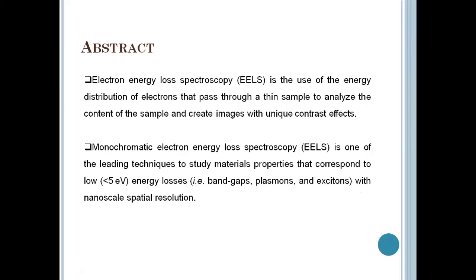These characteristics are observed in different energy regions depending on the energy loss. Electron energy loss spectroscopy is the use of the energy distribution of electrons that pass through a thin sample to analyze the content of the sample and create images with unique contrast effects. EELS instrumentation is typically incorporated into a transmission electron microscope (TEM) or scanning transmission electron microscope (STEM), which use high electron energies of 60 to 300 kV to interrogate the sample. The electrons must transmit through the sample, requiring an electron-transparent sample, and can interact either elastically (no energy exchange) or inelastically — it is these inelastic interactions that EELS exploits to extract information.